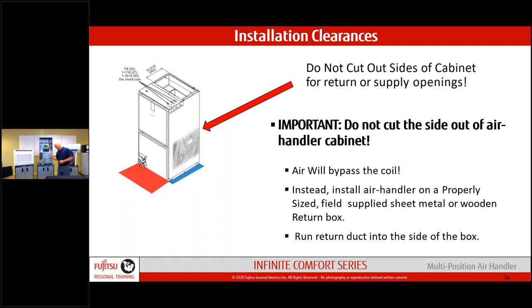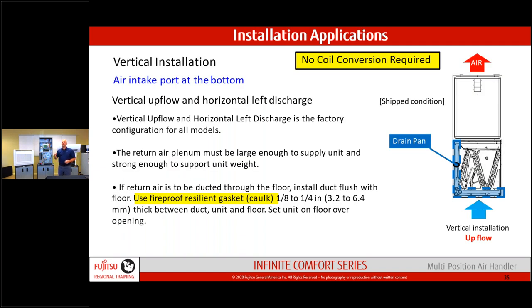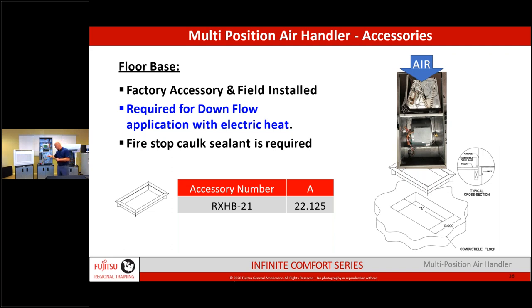When going vertical in downflow, use L-type support brackets on the side because the unit becomes top-heavy — the blower is underneath with the coil at top. Make sure the unit cannot tip over. If placing on a plenum underneath, the plenum must be heavy enough gauge to support the unit's weight. For going down through a floor, use the floor base kit and fire-seal around it. When going horizontal, inspectors will want fireproof caulk around the unit.